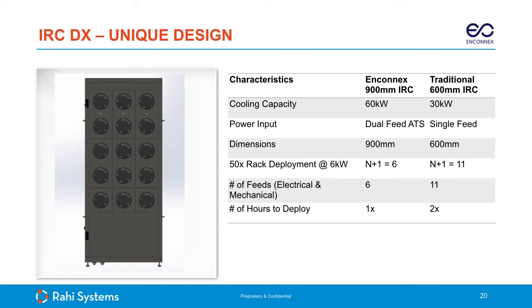Versus the competitor for the Enconnex brand, which would be the 30 kW, and it performed very well. You could design the system even at N+1 with just 6 units to cool the whole 50 rack pod, versus 11 units for the traditional unit. If you think about that, there's less mechanical feeds, less electrical feeds, and you can deploy the system in about half the time.